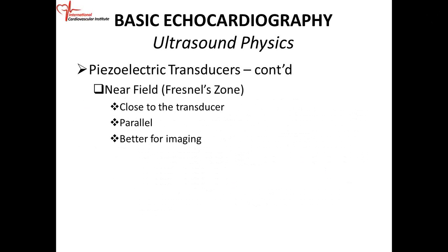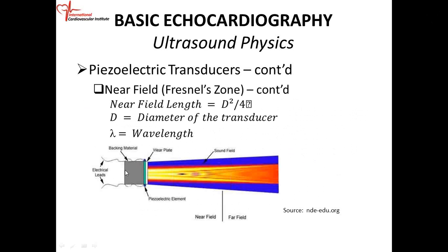And when you use your piezoelectric transducer, there is something called the near field, and there's also a far field. The near field is what we call the Fresnel zone, which is close to the transducer, and the beams tend to be parallel in that area, and it's better for imaging. So if this is your transducer right here, backing material, piezoelectric element, your wear plate, then when the ultrasound beam spreads out, you have a near field which is close to the transducer, then a far field which is further out.